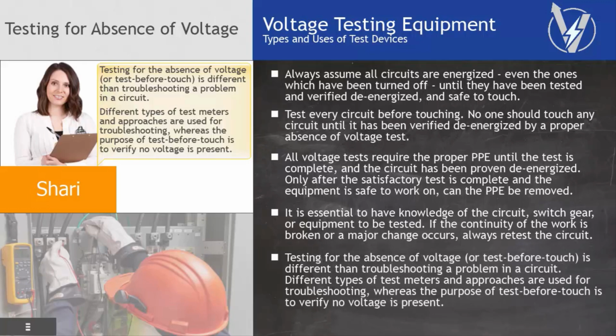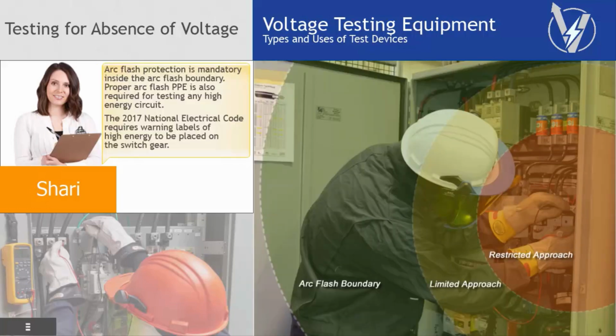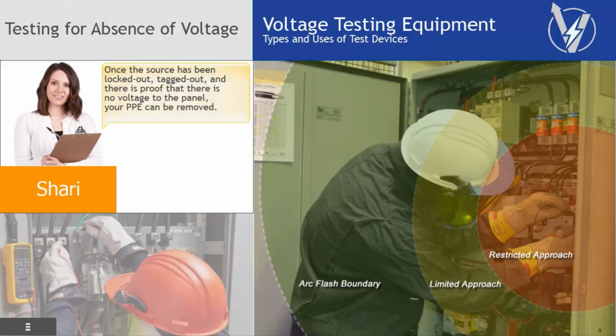Testing for the absence of voltage, or test before touch, is different than troubleshooting a problem in a circuit. Different types of test meters and approaches are used for troubleshooting, whereas the purpose of test before touch is to verify no voltage is present. Arc flash protection is mandatory inside the arc flash boundary. Proper arc flash PPE is also required for testing any high-energy circuit. The 2017 National Electrical Code requires warning labels of high energy to be placed on the switchgear. Once the source has been locked out, tagged out, and there is proof that there is no voltage to the panel, your PPE can be removed.